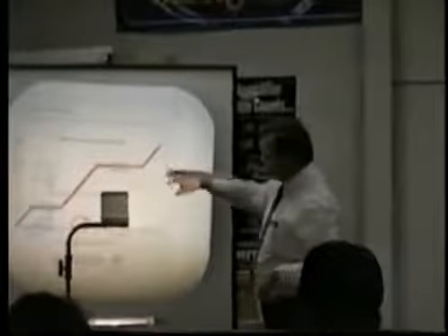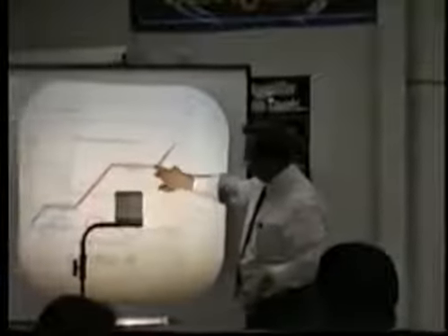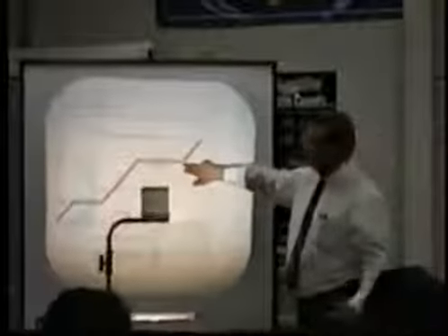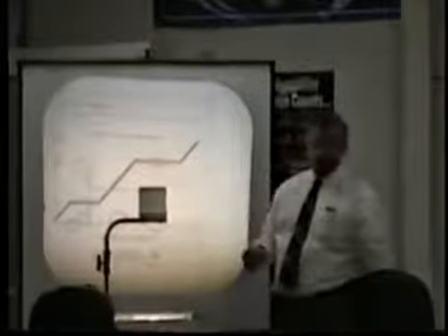If I went from vapor and removed BTUs, how many BTUs do I have to remove from a pound of vapor to get water? Almost 1,000, so 970, right? The word doesn't have to be steam, it's vapor. If I remove 970 BTUs per pound, I can end up with a pound of water.